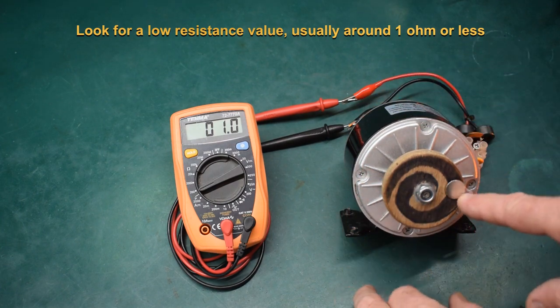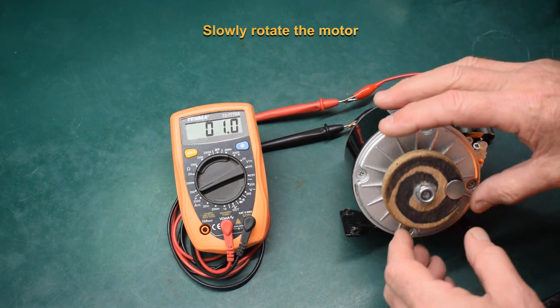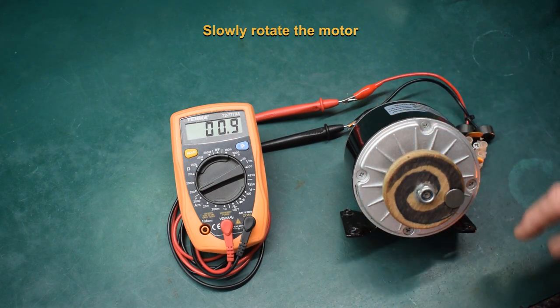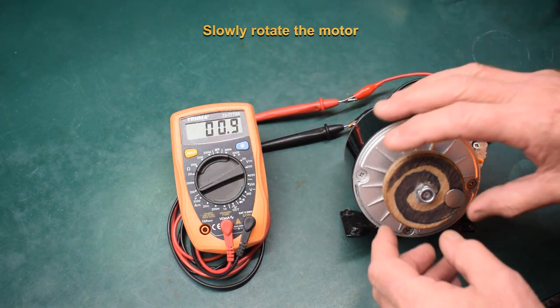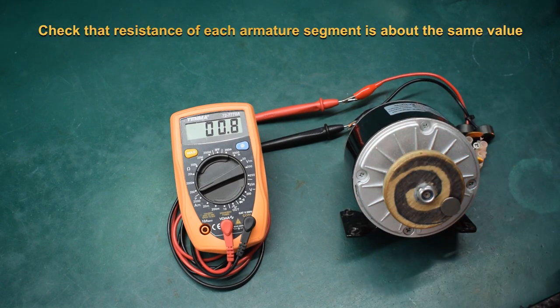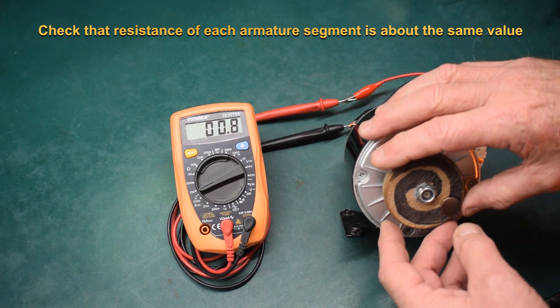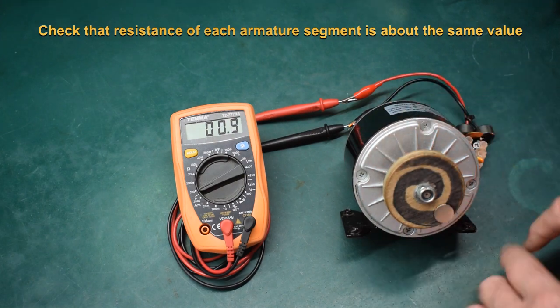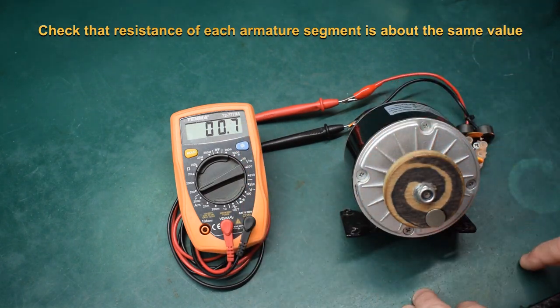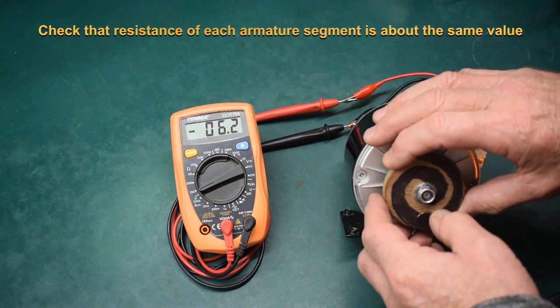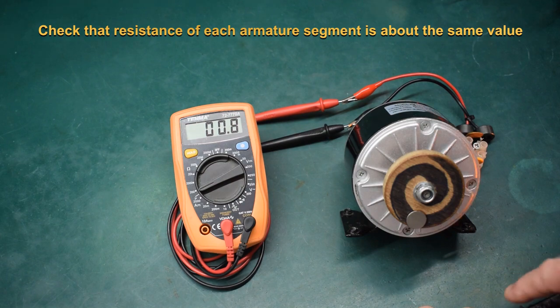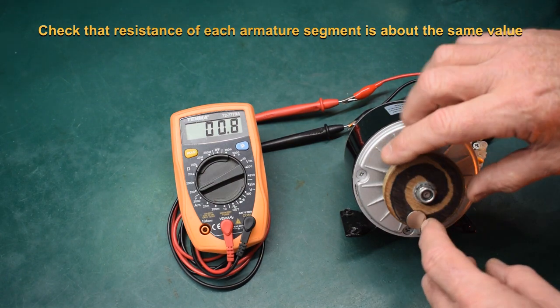Now what we're going to do is rotate the motor around, do it very slowly and look for the resistance of each segment of the armature. You can feel the armature moves in small notches and you can see that each time we're getting a reading of about just under an ohm. We're going to walk the armature all the way around.